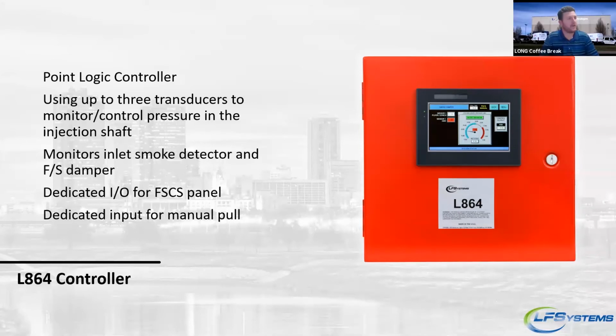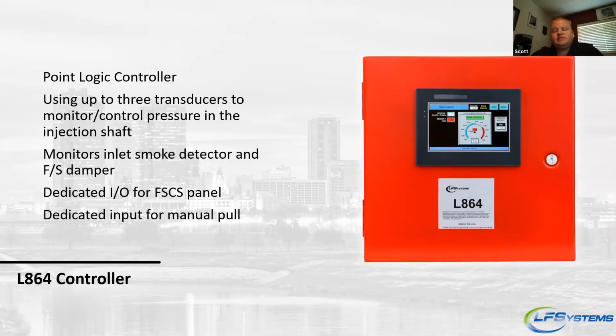Hey Scott, can you go into what's viewable on that L864 digital interface? Sure. So the L860 or L864 is fire engine red. It has a 7-inch color touchscreen monitor. You are able to monitor and view all the pressures within the stairwell. You're also able to see what the relief damper is doing. You're also able to see what the fan's doing. You can go in there and also manually change it if need be, and raise and lower the fan speed manually if you so choose.